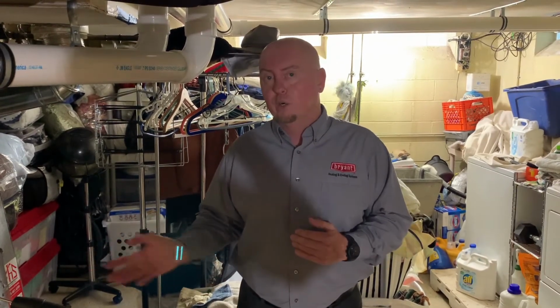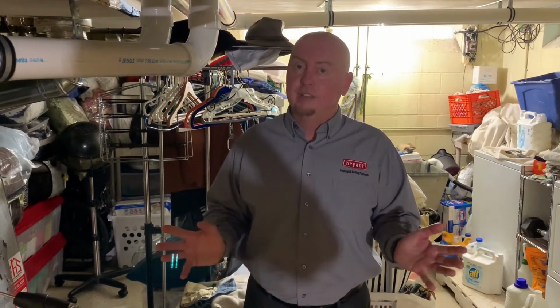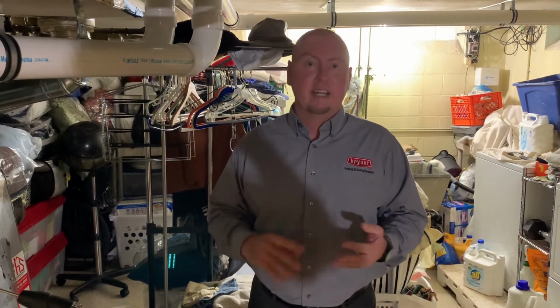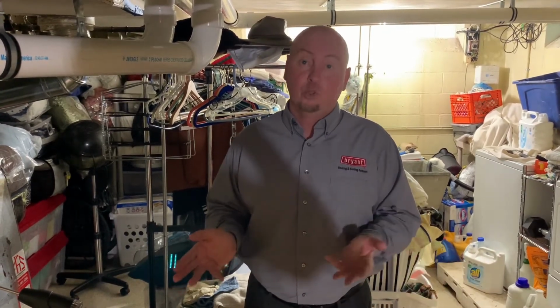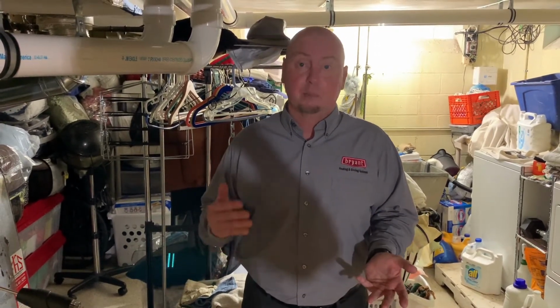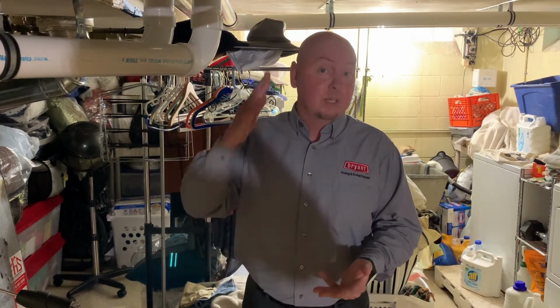So when you're looking at O2, be very careful on numbers you're looking at. I would say as a rule of thumb, 6 to 9% is a good number. Being a little bit high on that, 10, 11, 12, isn't the end of the world. You will see that on some 90-plus furnaces, depending on the vent diameter, 80-plus furnaces, depending on the flue pipe, the buoyancy through the chimney. So you can see a little bit higher.